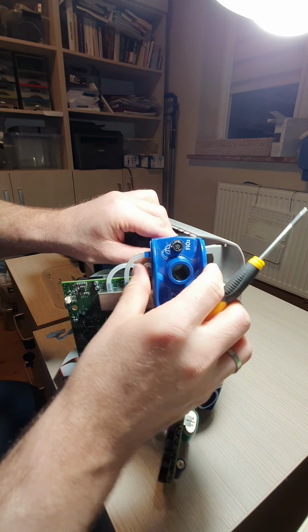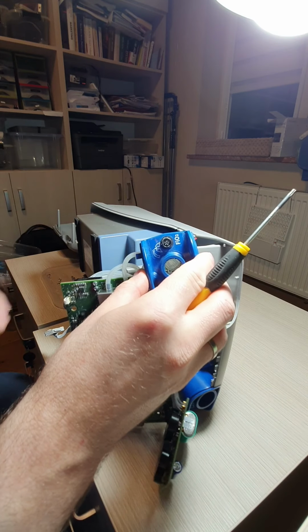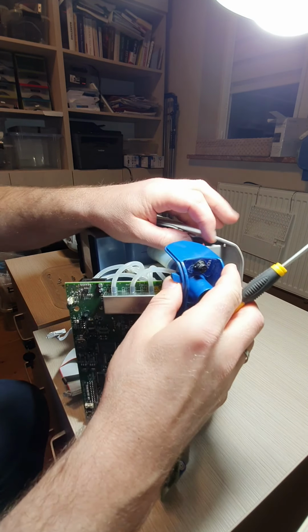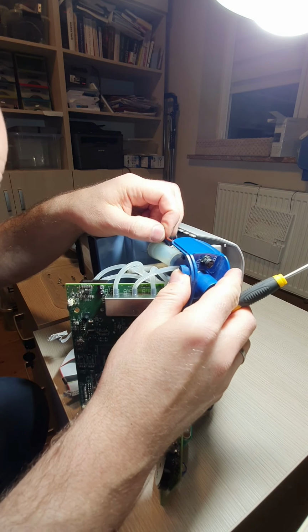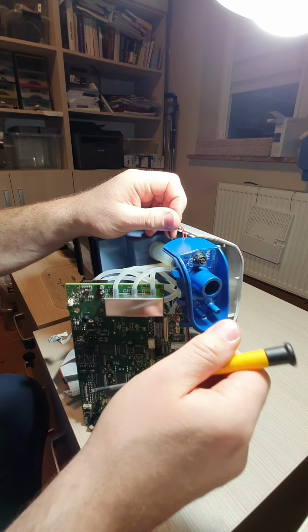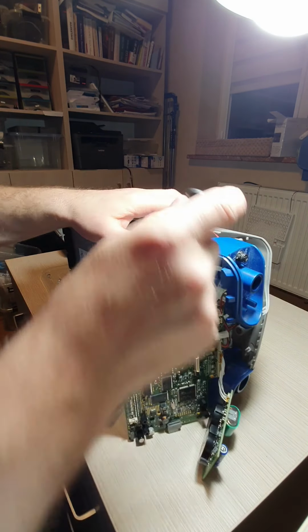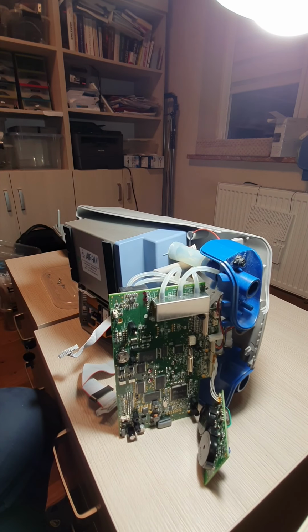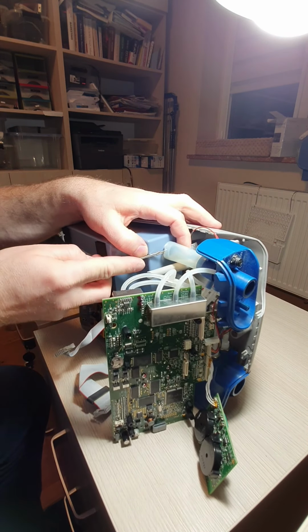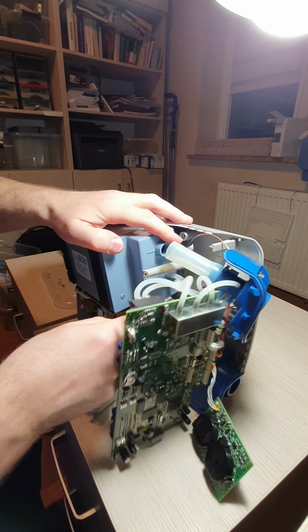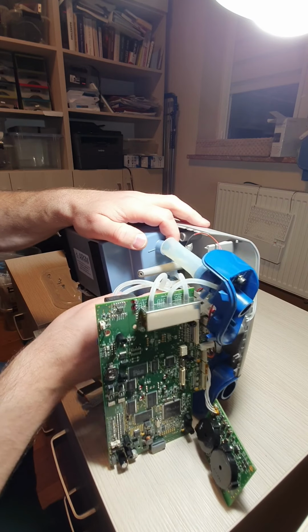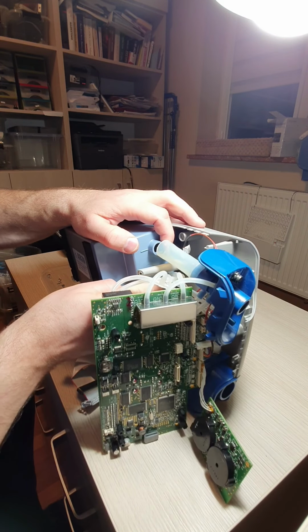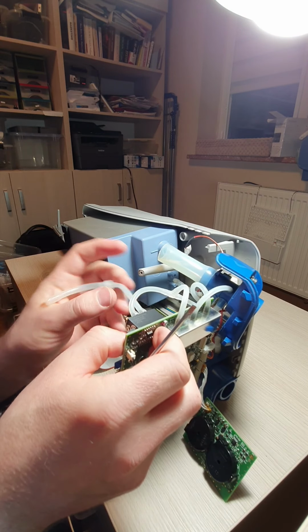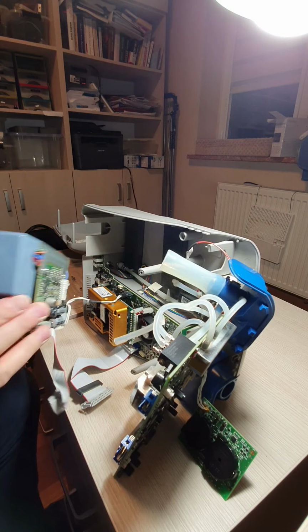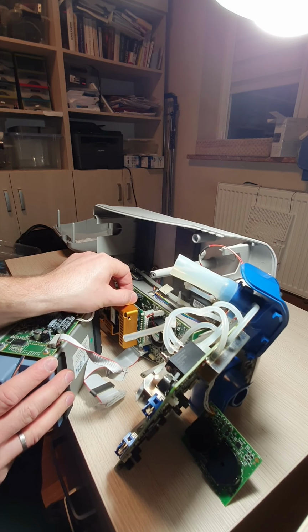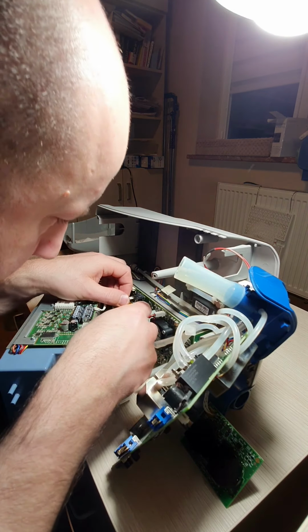pressure. This is the connection for the SPO2 sensor, which is this type of sensor. It is only 3 wires. Actually, it's two wires. It's simply a serial port. And so let's remove the turbine. So remove the oxygen port and remove the air source for the exhalation valve. This is the turbine. This is the plus 33 volts main supply for the turbine.